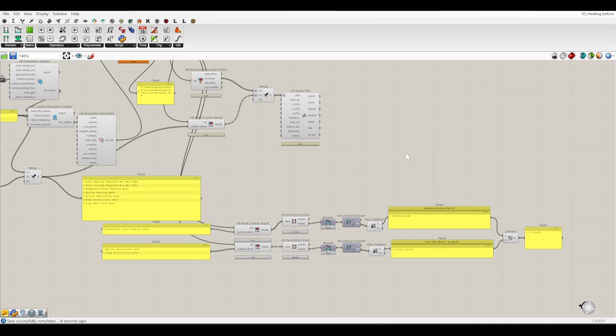Now let's look at what we can improve for this system. I have checked the EnergyPlus Input Output Reference, the boiler hot water documents here. So here's an example showing a more efficient condensing boiler. This one has 89% efficiency and also has a more accurate performance curve. So we are going to replicate this boiler in our simulation. I just copied it and I'm going to paste it here so that I don't have to go back and forth between windows.